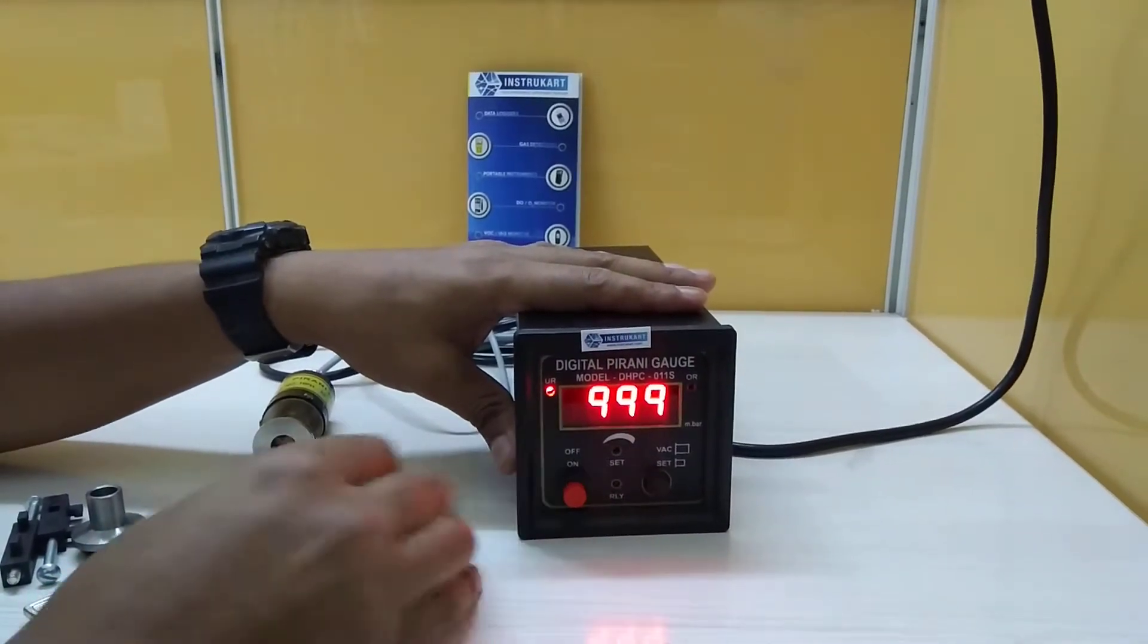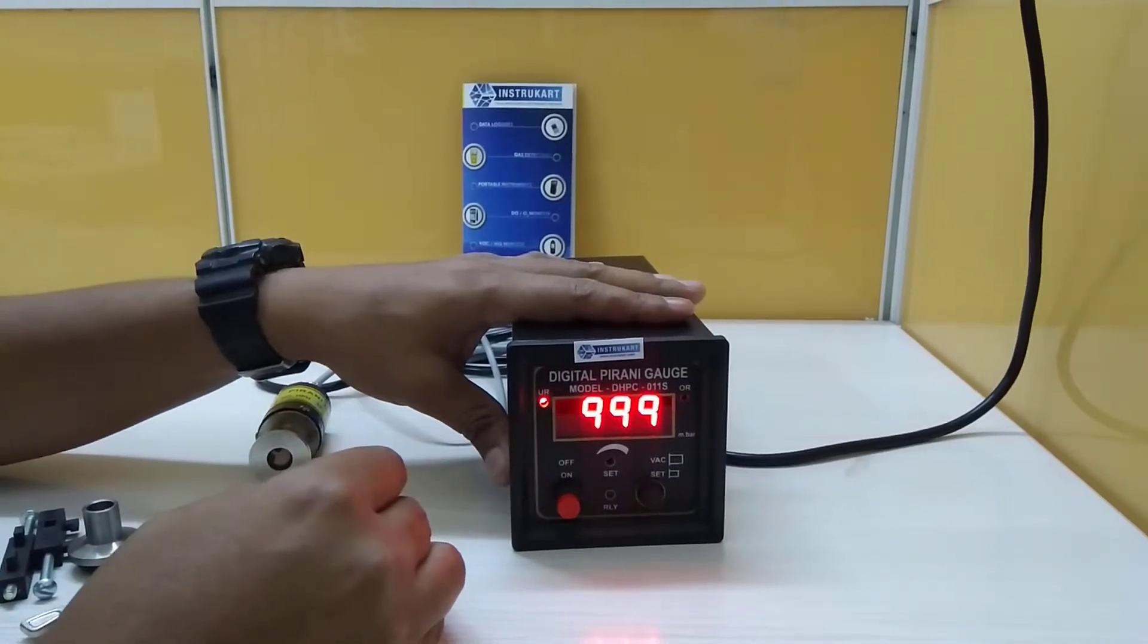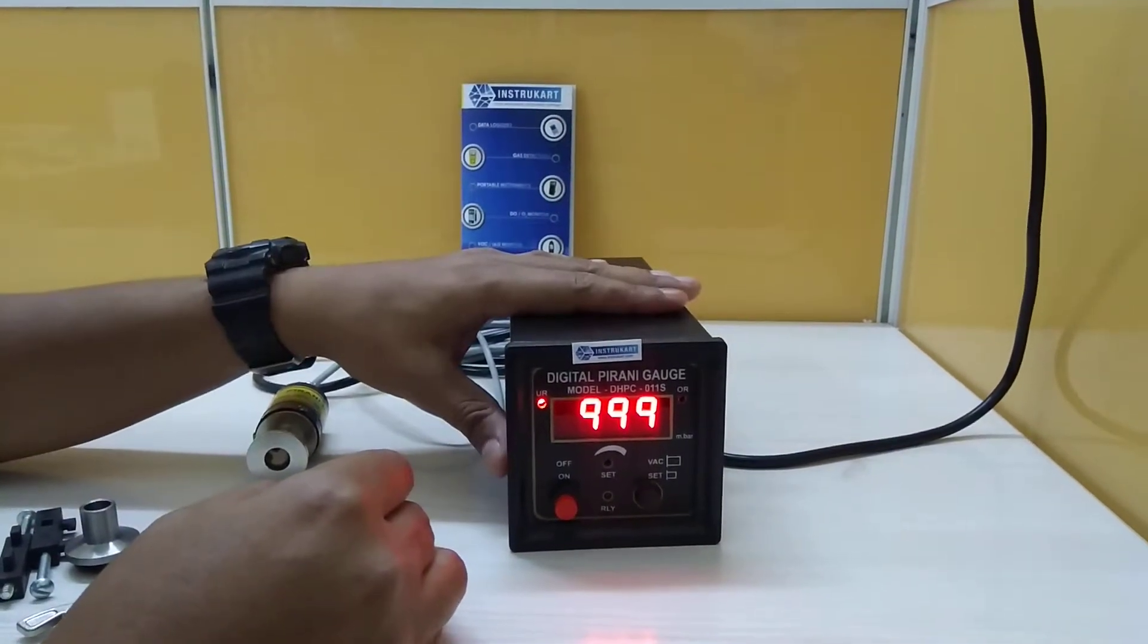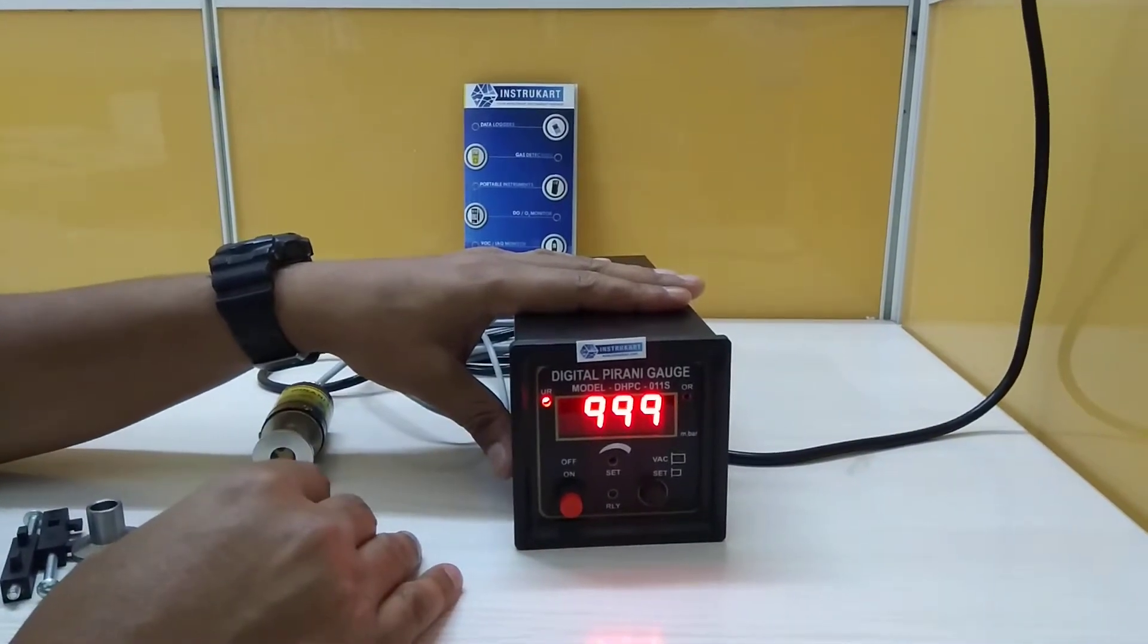On this Pirani gauge the range is 999 to 0.001 millibar and this is a model with the controller. It means that we can have a setpoint controlled at any vacuum range.